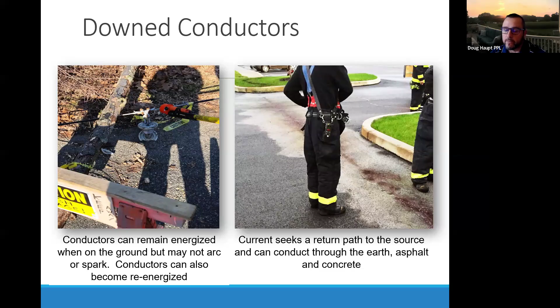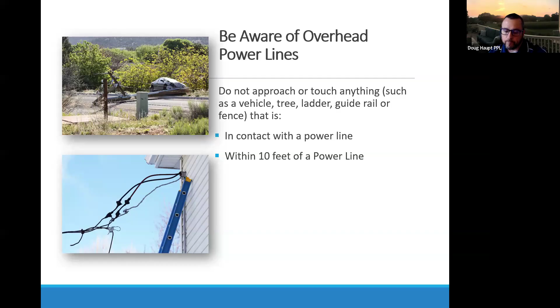By OSHA standards, not ours, as a non-qualified electrical worker, you need to maintain 10 feet to all of our distribution voltages, which are 3 wires on top of that wood pole, 1 wire on top. The neutral, remember, you have to consider the neutral as energized. You need to maintain 10 feet to it, as well as the service wire that's coming into the side of a building or your home as a better example. If you've got a service wire coming into a building on property, by OSHA standards, you are to maintain 10 feet to that wire as a non-qualified electrical worker. 10 feet.